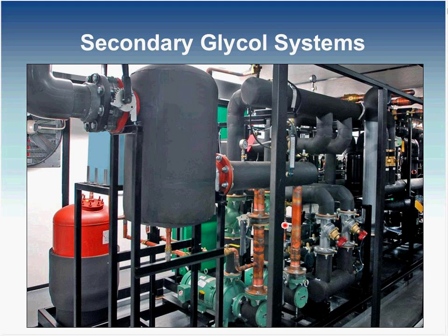A lot of it depends on how the system is designed, how it's installed, and how it's running. The cause for a potential increase in energy use is, first, you have a two-step heat transfer. First, cooling refrigerant that cools the glycol, so that's one step. Then you pump that glycol out into the store to cool the air, that's the second step. So when you have steps of refrigerant, the compressor has to work a little bit harder. Another way you can lose some energy is you have pumps running there. Pumps consume some energy, so you're using a little more energy to pump that glycol out and around the store. Again, with design, installation and operation, those energy losses can be minimized.